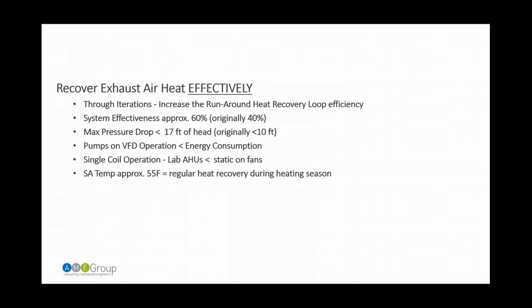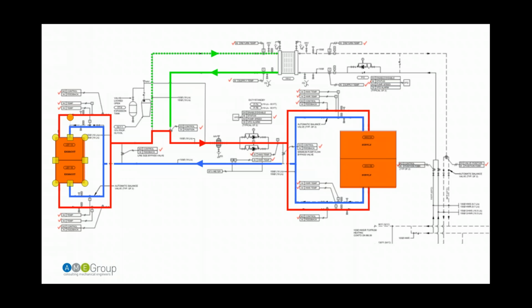And our supply temperature is really going to be maintaining around 55 degrees because of the reduction in airflows that we're going to get into later as well. But that really helps us be able to recover heat throughout most of the heating season. And so this is really what our system looks like.